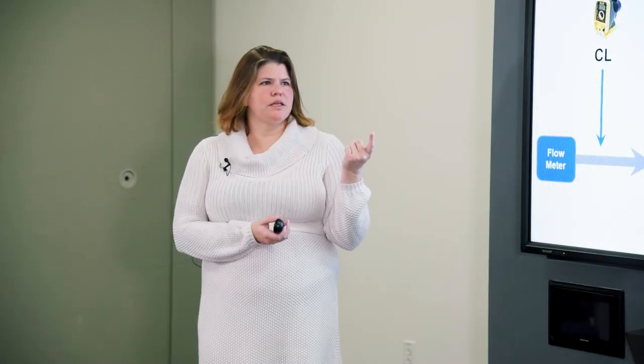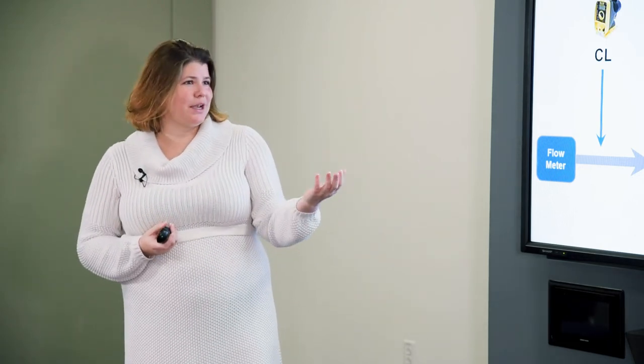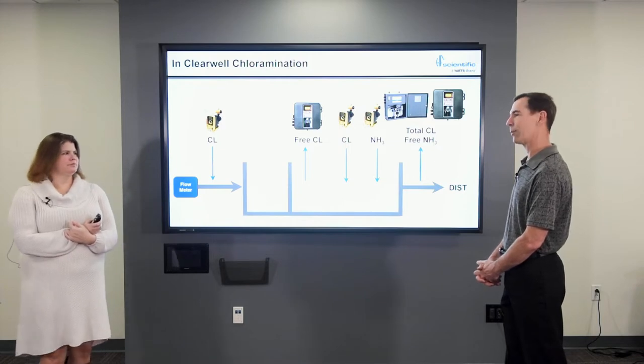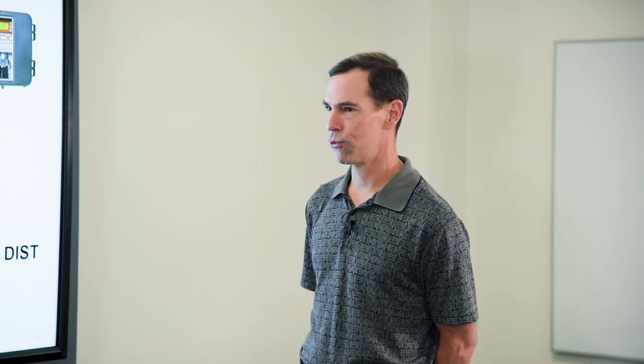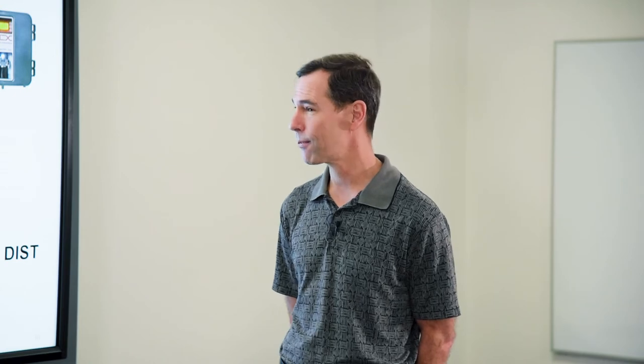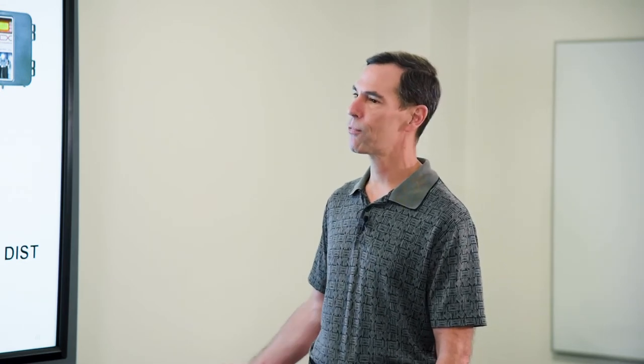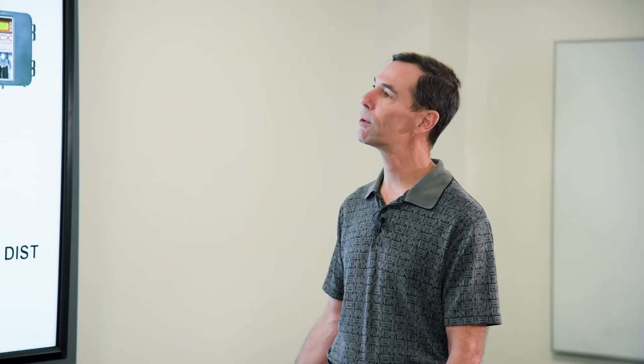One of the challenges of in-clear well chloramination is actually getting the chemistry into the system and well mixed. Getting the chemicals distributed across a large body of water can be very challenging, and can make the results less than desirable because of the flows, currents, and mixing naturally taking place. Typically you would like to have some sort of a mixing or wide-area distribution system if you're doing in-clear well chloramination. Some customers have a weir-type system where they can put a spray bar adding chemical and mixing at that overflow point.